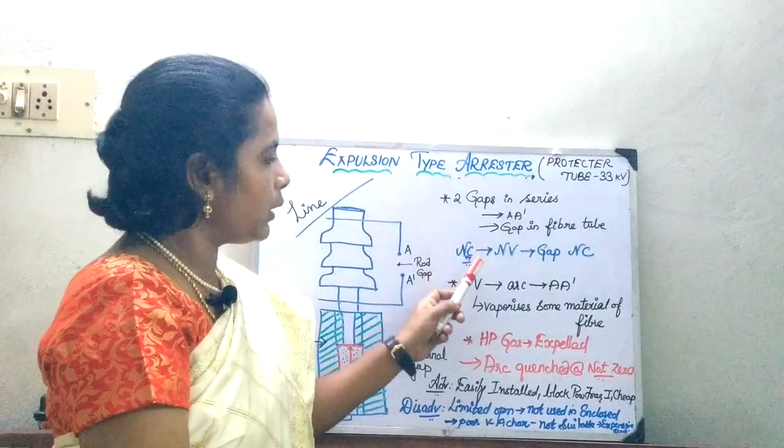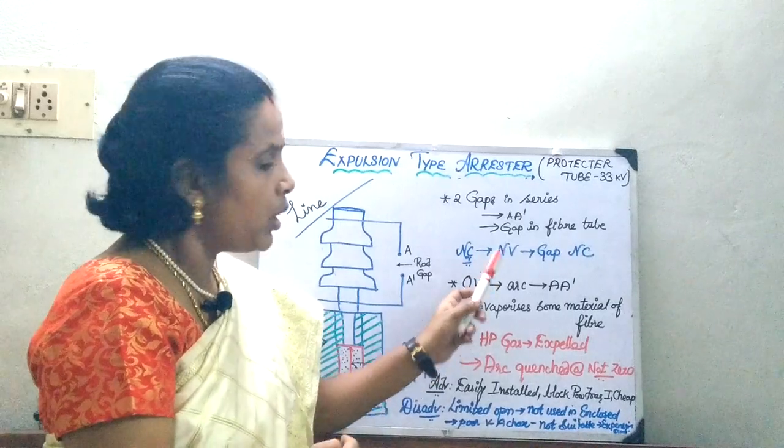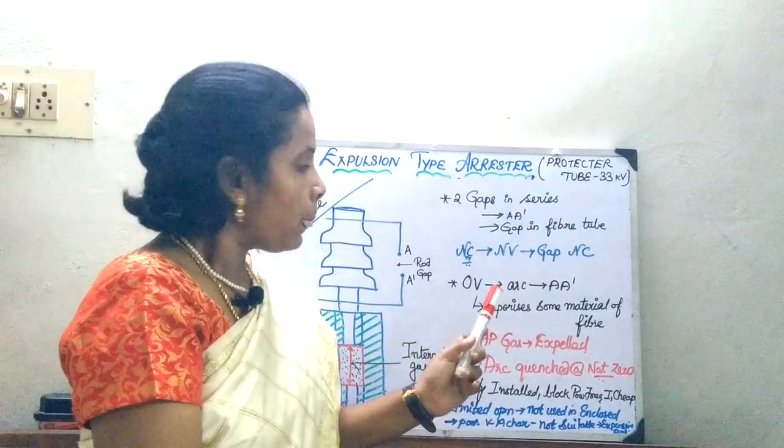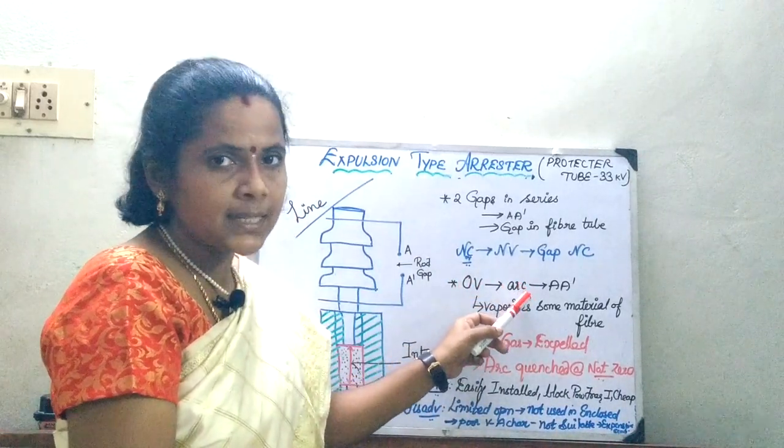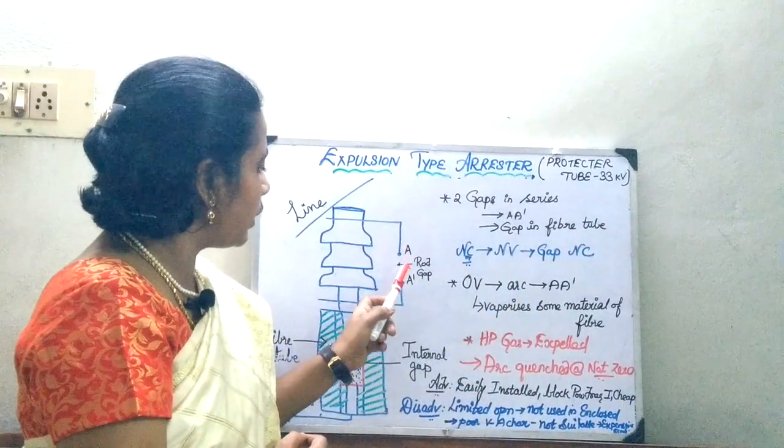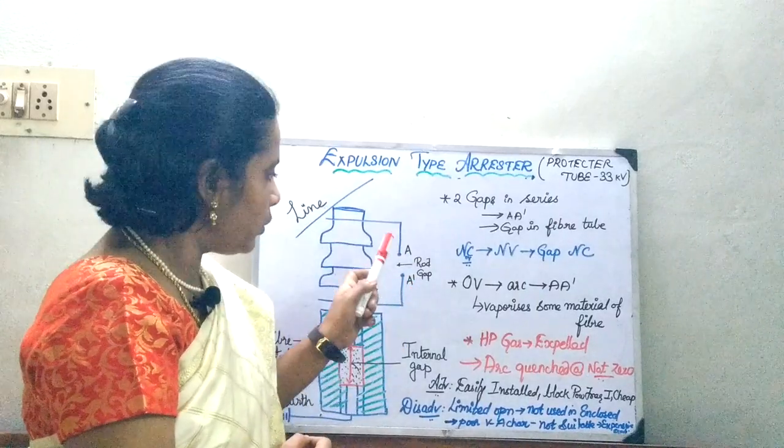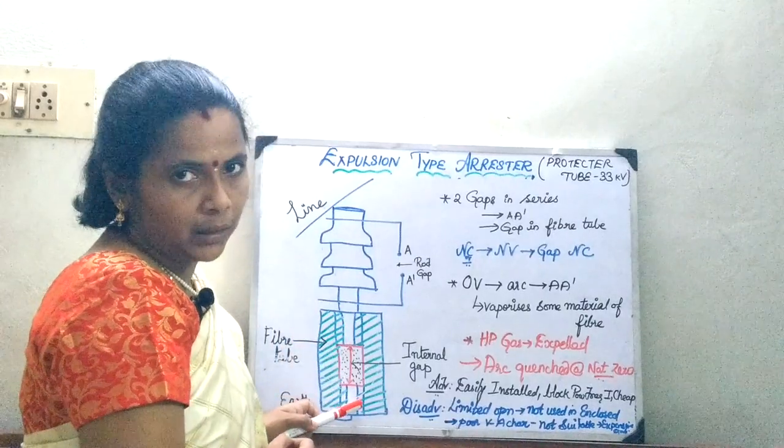Whenever under normal condition, the normal voltage will not be sufficient enough to cause a series sparking of both the gaps. Now, under over voltages, the arc which is going to be created due to this over voltage, it is going to create arc between the path A, A dash. Now, this arc or this rod gap, it is going to be in series with your fiber material.